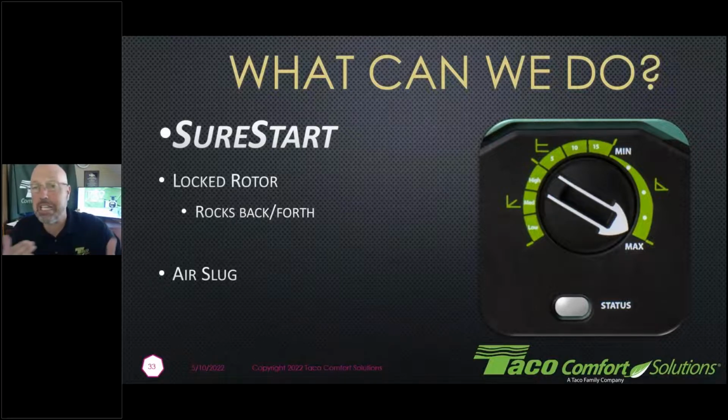You're going to see these flashes of light, and it may make a little bit of noise and be a little disconcerting in the beginning because, hey, my standard PSCs never did that before. This is doing stuff on purpose and trying to get those air bubbles out of there. Like I said, you don't make it happen. It does it all on its own to give you a longer lifespan out of these circulators, to prevent the premature failures of circulators that are running out there, based upon system conditions and water conditions.